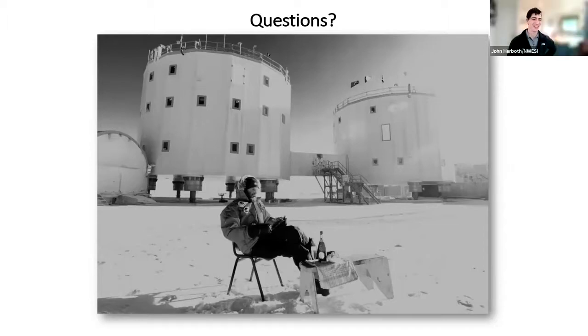Yeah, I can answer Carrie's question real quick. Yeah, sure, go ahead. The fire marshal is always correct, but the code says 24 inches. And if you're going to do 24 inches, you got to put a wrap around it. So technically, the code says one thing, but the fire marshal overrides. And Carrie's question is about how far away can the actuator and the damper assembly be from the fire rated wall or compartmentalized? Typically your blades are supposed to be in the plane of the wall. Correct. They're guarding the wall. You can put them up to 24 inches out if you put a thermal blanket around them. Or if the fire marshal or building official says something's okay, then it is. Then document. They're the ones who judge. Well, yeah.